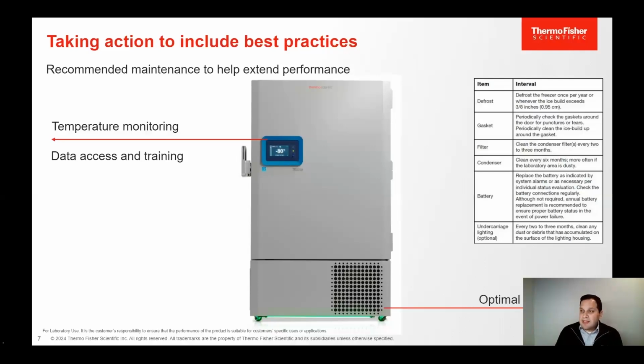In this checklist of preventive maintenance periodic intervals, we consider that the unit should be in optimal environments. They are quiet, and they have minimal heat load rejection into the facilities, but that's best accomplished by checking the filters behind this grate, as well as checking for dust and cleaning the condensers. That can be done every 2 to 3 months.